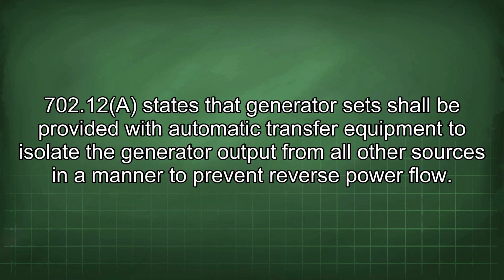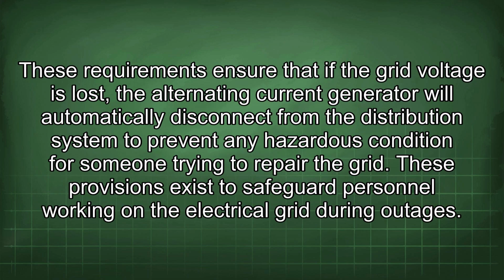702.12 states that generator sets shall be provided with automatic transfer equipment to isolate the generator output from all other sources in a manner to prevent reverse power flow. These requirements ensure that if the grid voltage is lost, the alternating current generator will automatically disconnect from the distribution system to prevent any hazardous condition for someone trying to repair the grid. These provisions exist to safeguard personnel working on the electrical grid during outages.